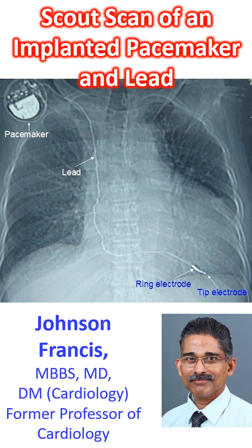The initial image obtained during CT scanning is usually called a scout image, pilot, or topogram. Sometimes it is also called a scanograph. The scout image is used to determine the extent of slices to be taken during an axial scan. The tube is kept in a fixed position and the table is moved as the X-ray beam is delivered to record the scout scan. The scout image is similar to a radiograph in appearance.